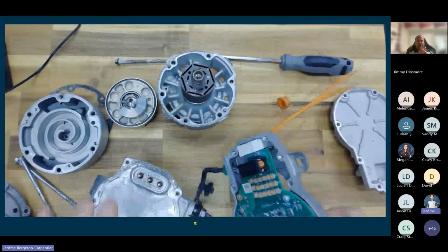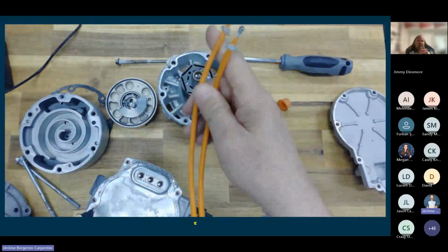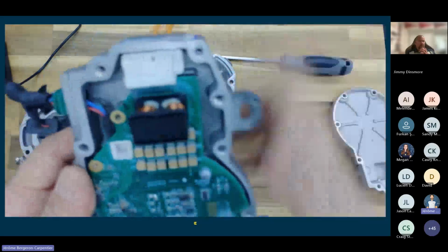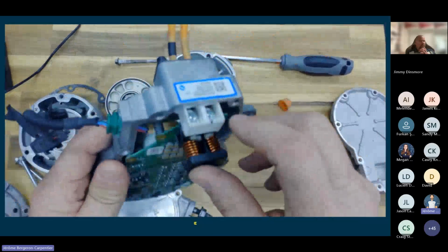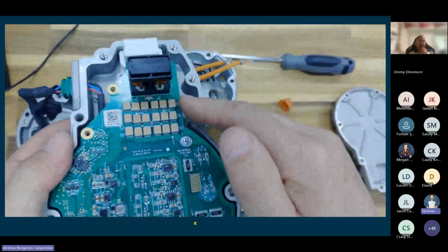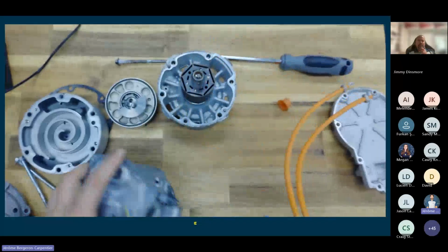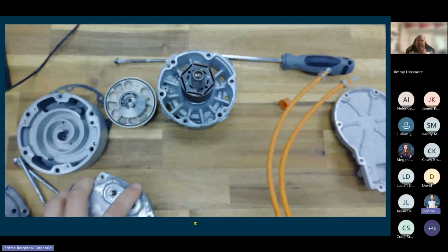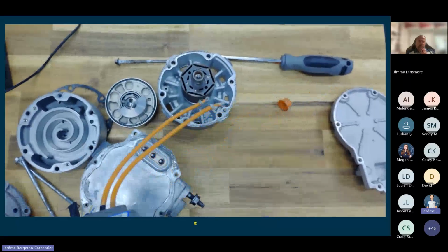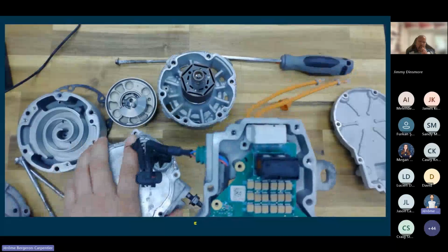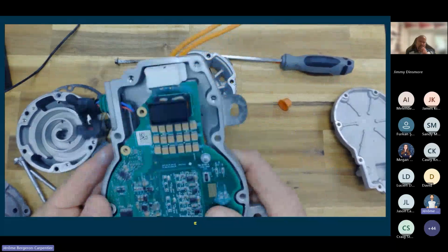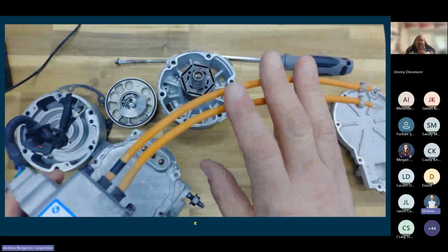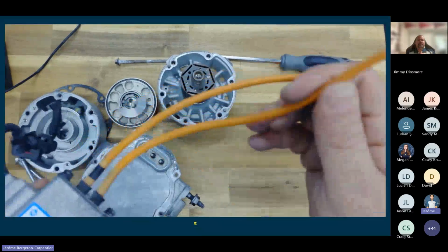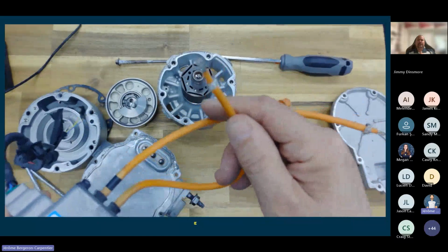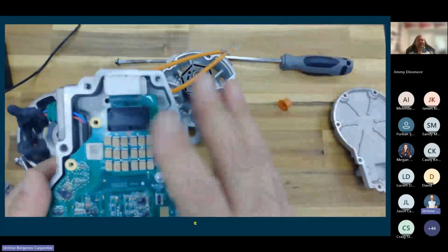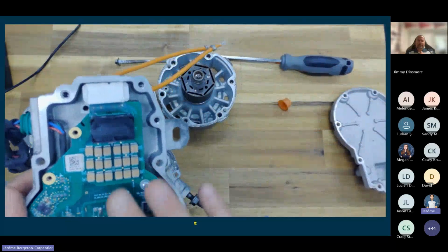Now, if I was going to test it, and this is also an important point, remember I was putting high voltage insulation test through this line that goes through the back here, through the little screws here into the isolators, which goes into the board. So I'm not actually directly testing the stator windings in this unit itself. So unless there's a short to ground or case to ground, and I'm testing it through the unit itself, it may be difficult to get a proper reading from it. And this is why a lot of manufacturers say, be aware, if you're going to do an isolation test, follow OEM procedures, because I shouldn't just throw 1,000 volts or even 2,000 volts in some cases for isolation checking through the unit, because I may be going directly through electronics to do that. So I could wind up damaging the electronics.